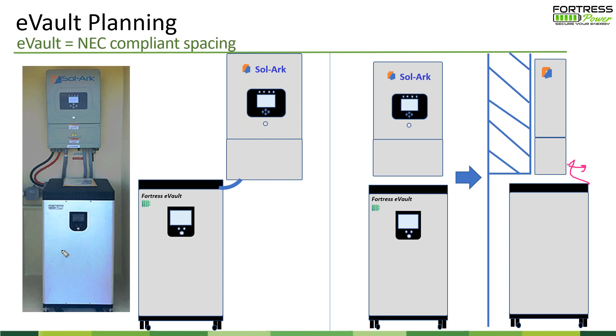The DC input on the Sol-Ark is here, and the DC wiring from the eVault can go out either end. Putting the eVault to the left of the Sol-Ark makes a code-compliant and convenient cable run between the two pieces of equipment. If you want to get fancy, you could build a false wall and bring the Sol-Ark unit out from the wall, tucking the eVault into the wall to make up that dimensional difference. That could work well on a slightly larger project.